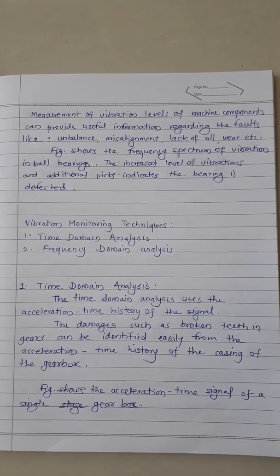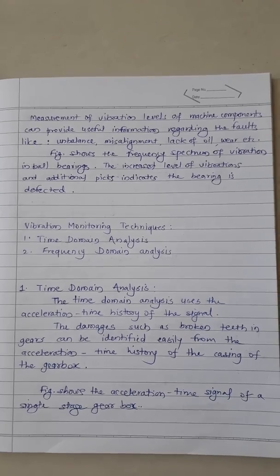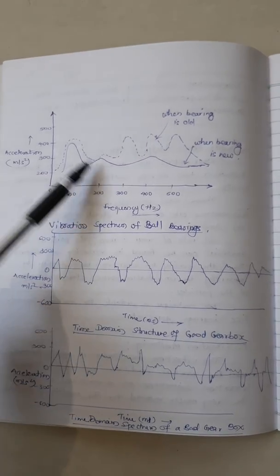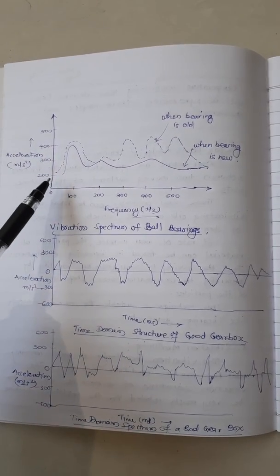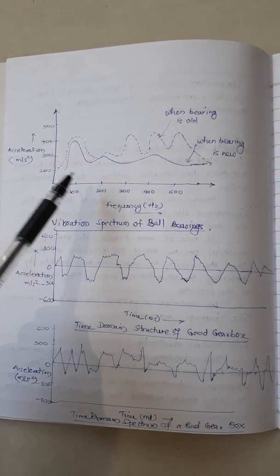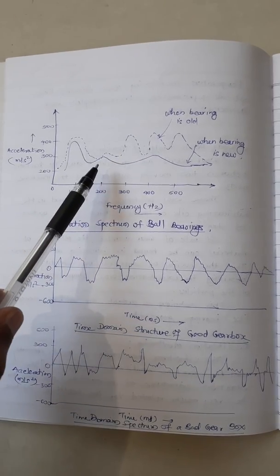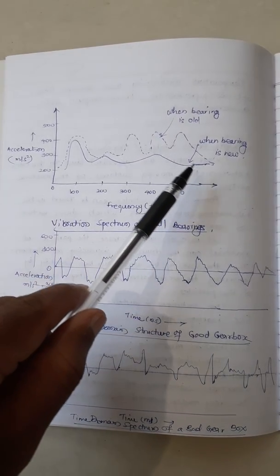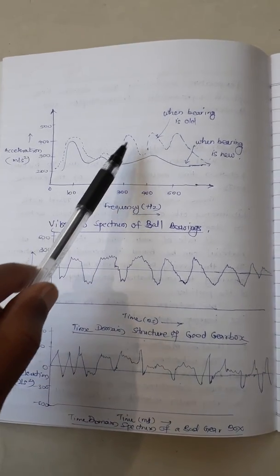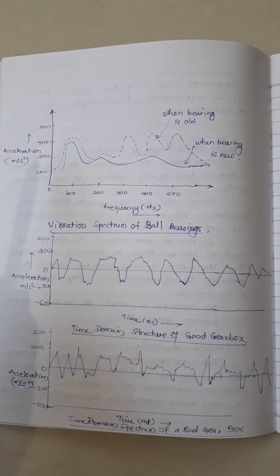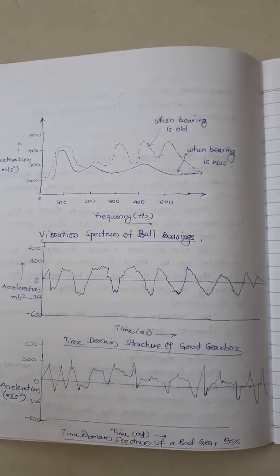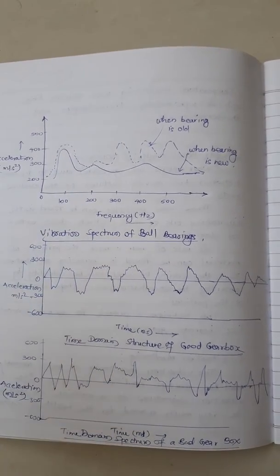The figure shows the frequency spectrum of vibration in ball bearings. The increased level of vibration and additional peaks indicates the bearing is defective. Looking at the frequency versus acceleration plot of the bearing: when the bearing is new, the graph shows a baseline. When the bearing is old or worn, changes in the graph such as increased acceleration can be seen, indicating wear and tear in the bearing. This is the vibration spectrum of a ball bearing.